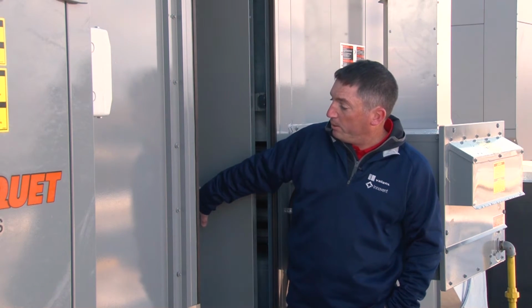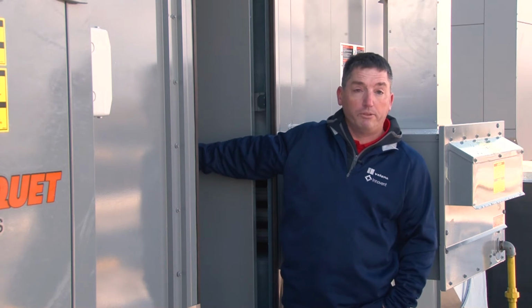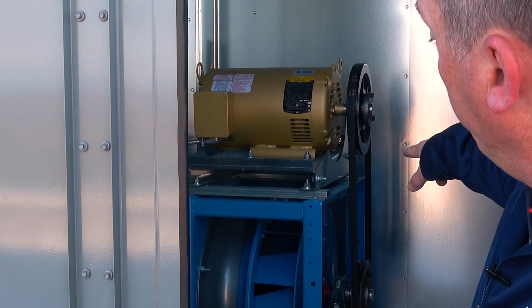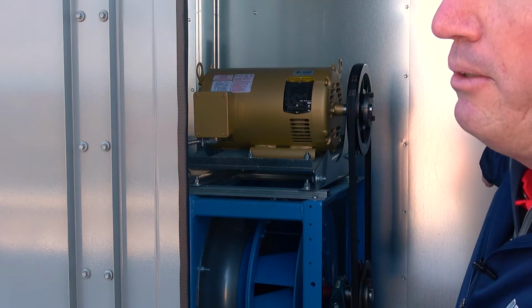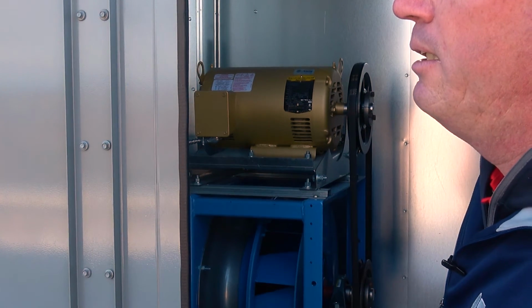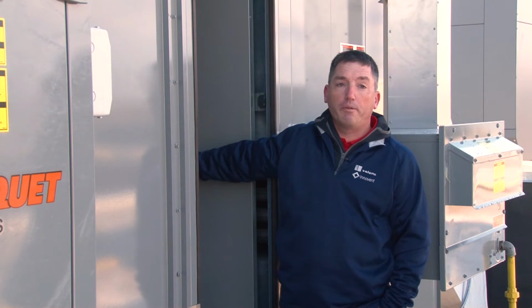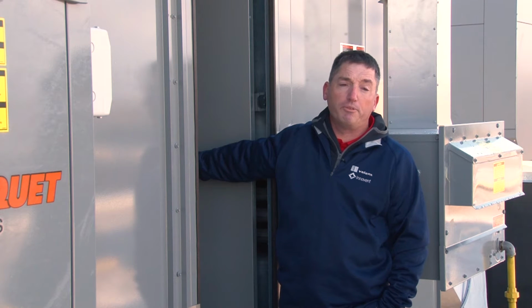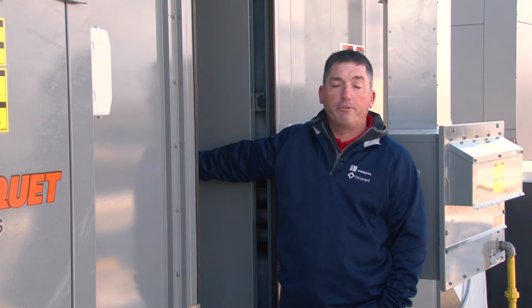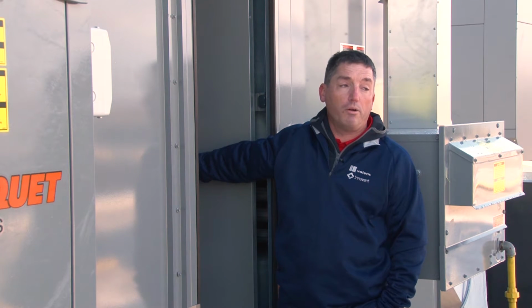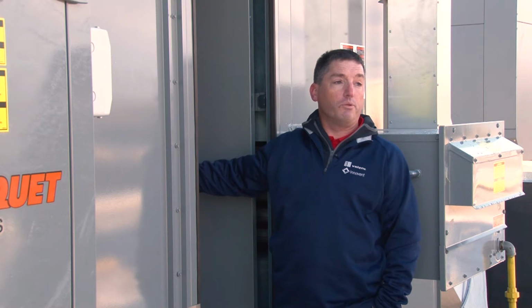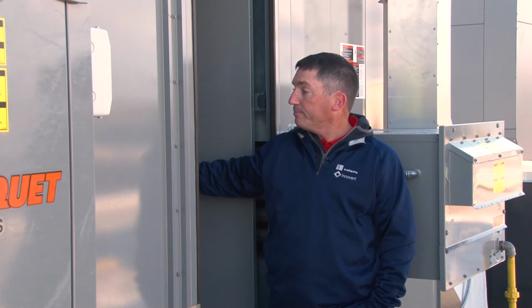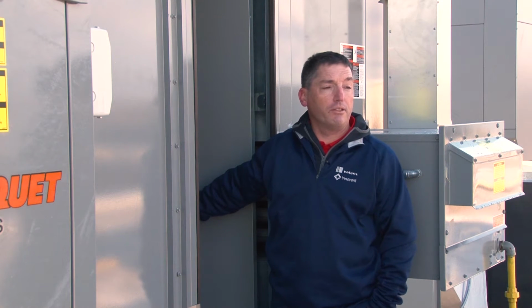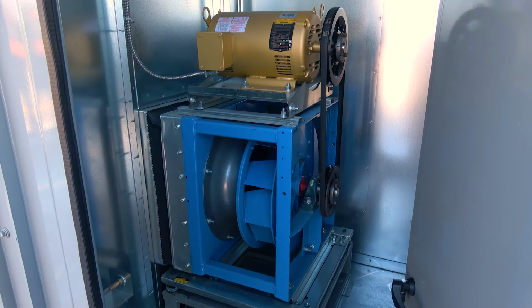So the supply blower, as I mentioned before, is belt driven. So we have a B-section belt. The usual service recommendation, as I mentioned before, is filters approximately every 3 months, and then belts either every 6 or every 12 months. Because the unit does run 24/7, 365, it's probably best to err on the side of changing it more frequently rather than waiting until it fails.